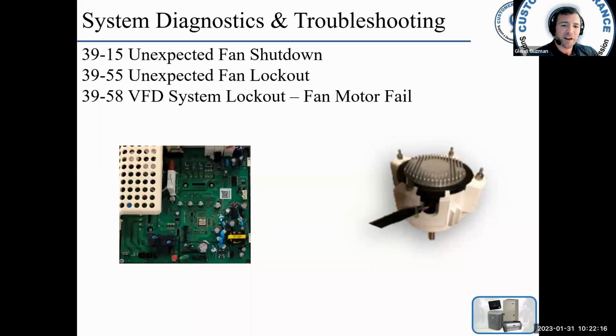3915 unexpected fan shutdown, 3955 unexpected fan lockout, and 3958 VFD system lockout fan motor fail. These codes are a little peculiar, and the manual isn't very helpful at times, it seems like. 3915 is declared when the VFD commanded speed is above 200 and the actual speed is reduced to less than 80 RPM for 10 seconds.